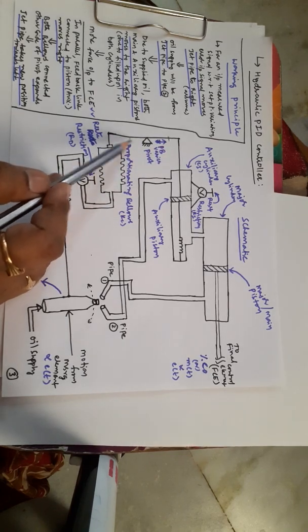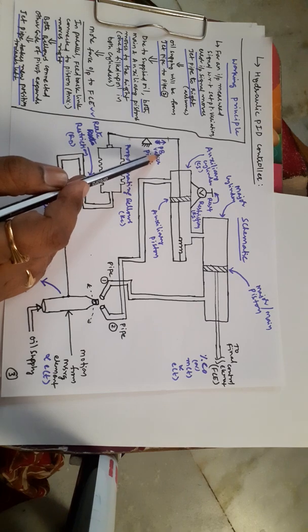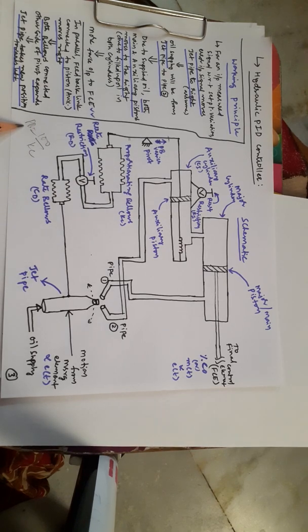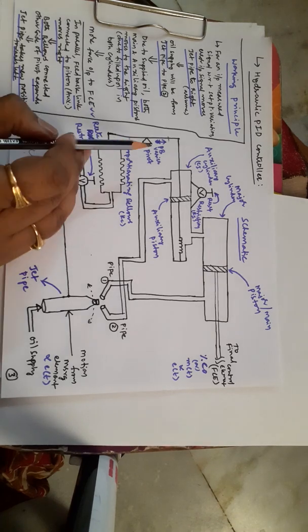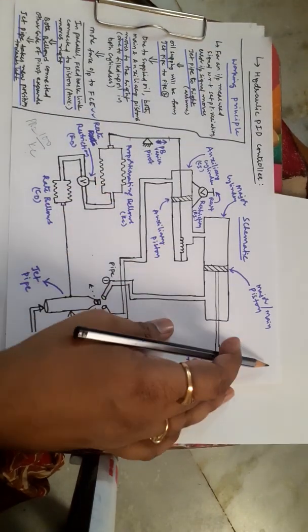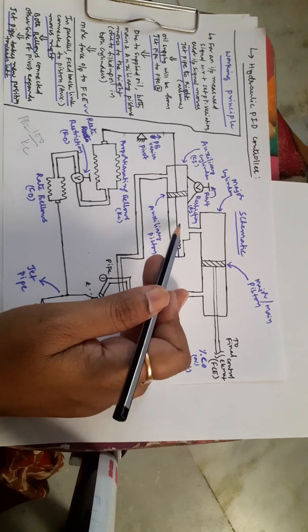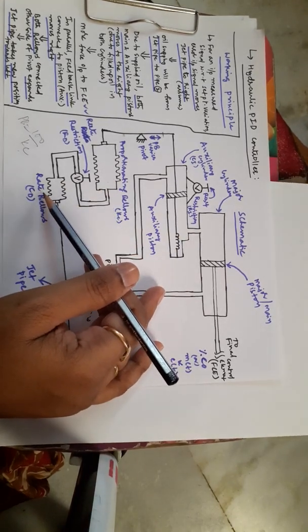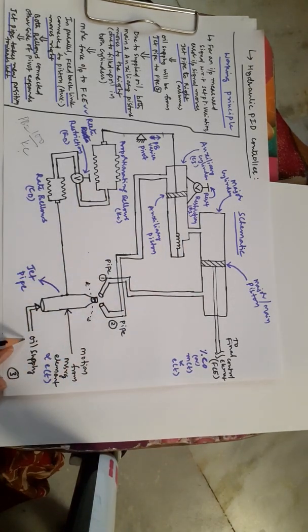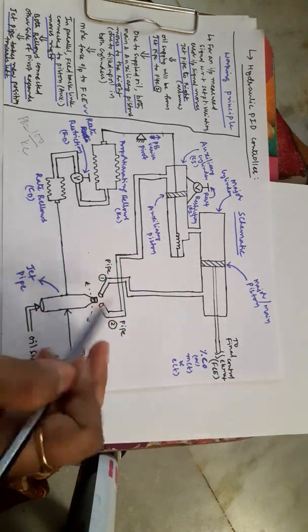The pivot position can be moved in either direction based on requirement. Moving the pivot adjusts the proportional band value. The proportional band is 100 divided by K_c, so any variation in pivot position impacts the K_c value with respect to the proportionating bellows. The main elements are: main cylinder, auxiliary cylinder, proportionating bellows, rate bellows, reset restriction valve, rate restriction valve, pipe 1, pipe 2, jet pipe, oil supply, motion from measuring element, and output to final control element.